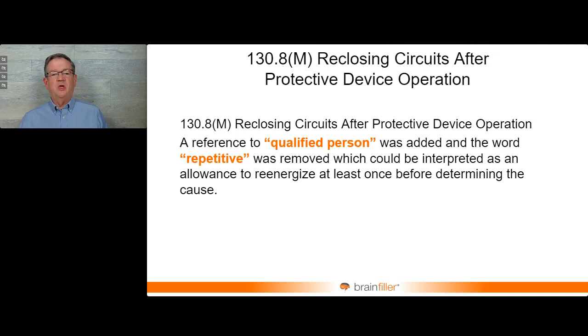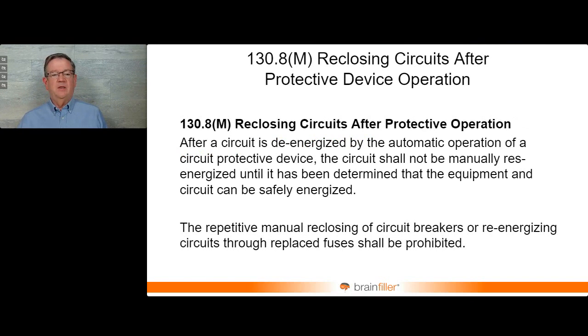There was language in there about repetitive, which implied, oh, well, we could try it once. We just can't do it again. Well, even trying it once, if there's a pretty bad fault out there, it may not end well. So the rules are now, you have to have a qualified person investigate why did it trip?